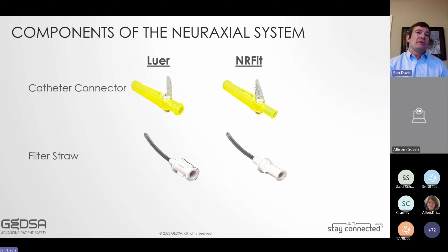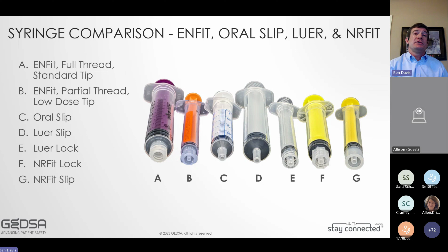Another thing I wanted to mention is within ENFit, you can have a full thread syringe or a partially threaded syringe. So syringe B is a partial thread. They're both ENFit. They're both 100% within the standard and acceptable. But depending on who your manufacturer is or what the application is, it may be full thread or it may be partial thread. B also has a low dose tip. C, just for comparison, side by side here, is an oral slip. D, you can see how a Luer slip stacks up against that. E is a Luer lock, and then moving into NRFit, we have our NRFit lock with F, and then NRFit slip with G.